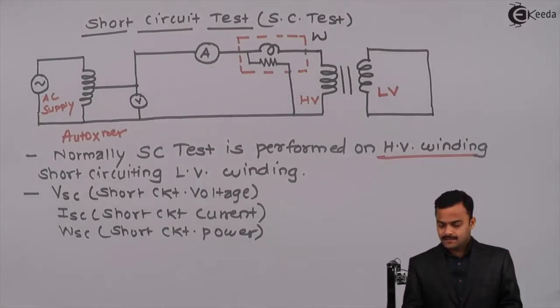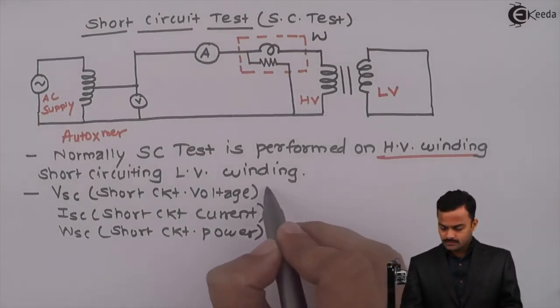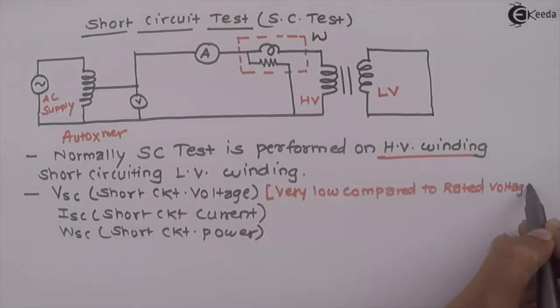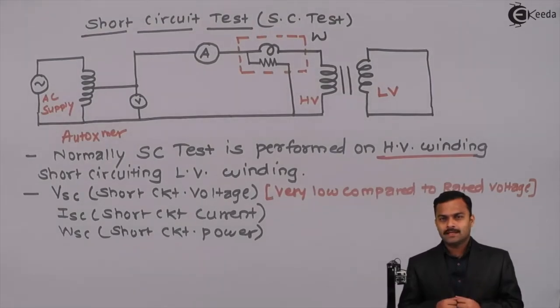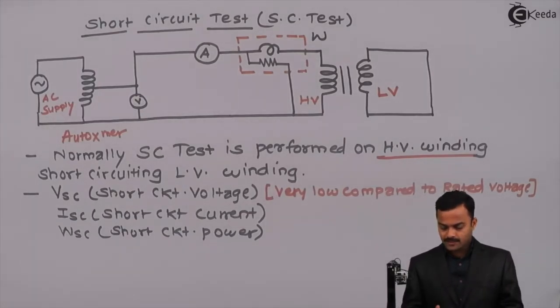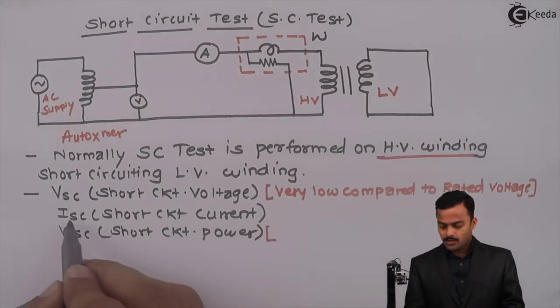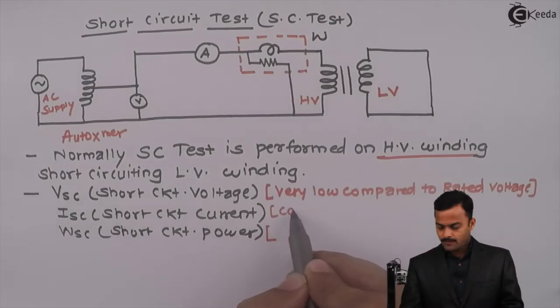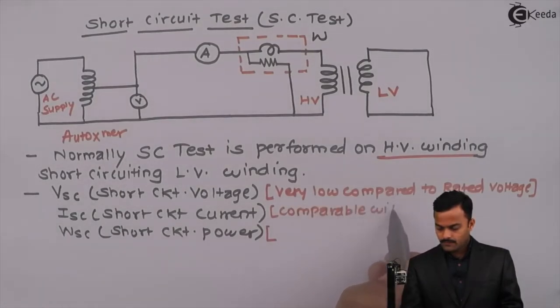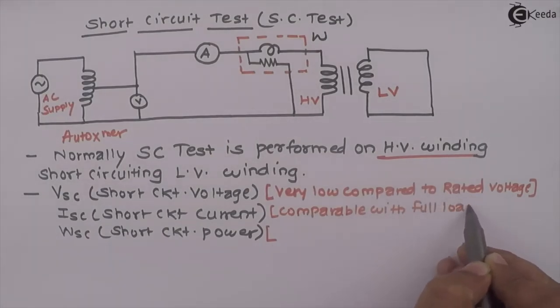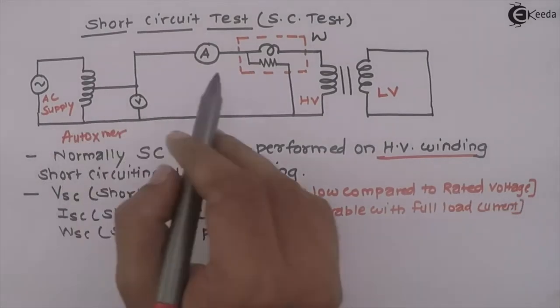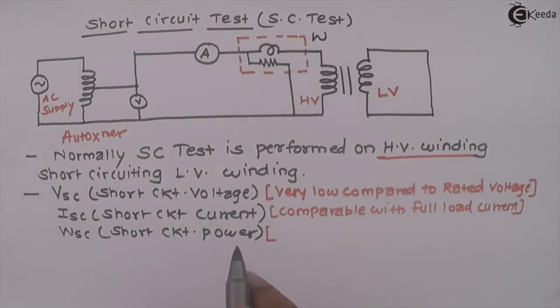VSC is very low compared to the rated voltage. If voltage is very low, the losses that depend on voltage — core losses — will also be less. Hence, the wattmeter will not measure core losses, or they will be very less compared to copper losses. Copper losses will dominate because the short circuit current is comparable with the full load current, so a significant amount of current flows through the windings.